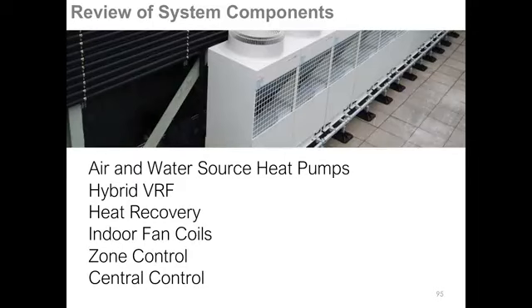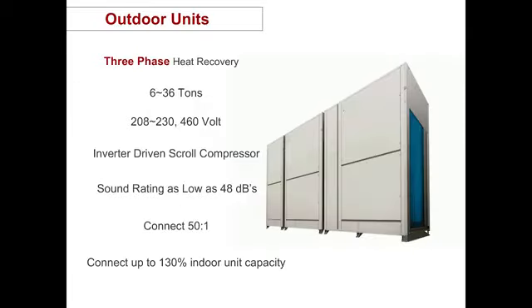All right, so let's go over the components. We have air and water source heat pumps, hybrid VRF, which is already available overseas. They've been talking about it for 5 years or more, bringing it here. Heat recovery systems, indoor fan, coils, indoor units, zone control, central control. All right. So typically you have an outdoor system that can be anywhere from 6 to 36 tons. Some manufacturers even have larger combined units. Somewhere the voltage 208, 230, or 460 volt, inverter-driven scroll compressors. Sound ratings as low as 48 decibels. Connected units 50 to 1. And connect up to 130% of indoor unit capacity.